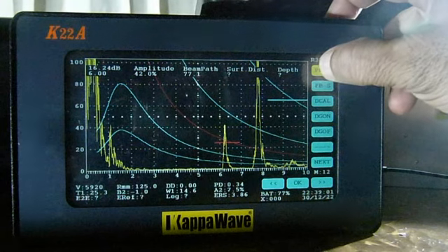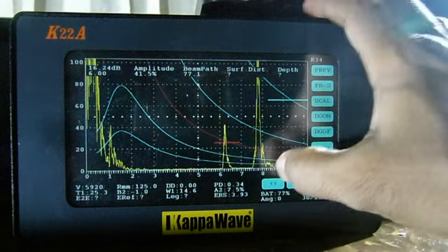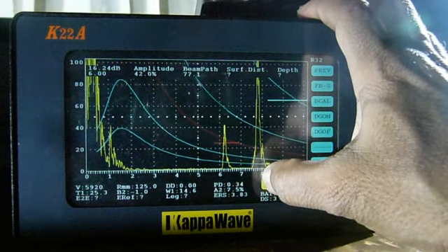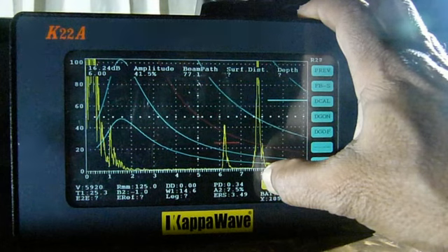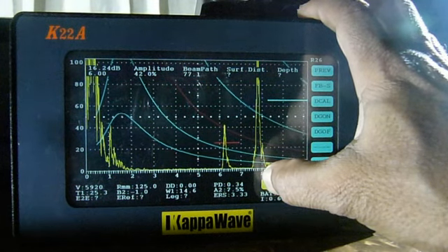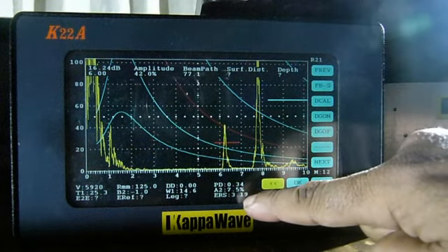We will now calibrate the DGS curve. The curve is calibrated with the echo for correct ERS value. It shows an ERS value of 3.19 mm.